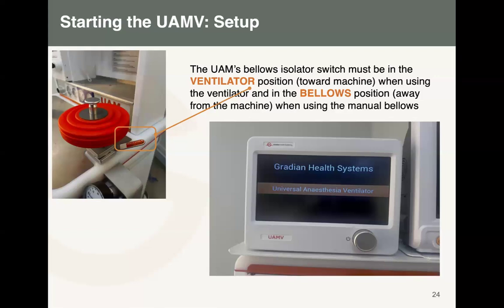We advise you to switch the bellows isolator switch first to the ventilator side, and then that's where you start your vent. And when you are almost finishing up with the case, you want to go back to manual ventilation. You have to end the case from the vent, then come down, change the isolator switch to the bag side, and then continue to ventilate the patient.